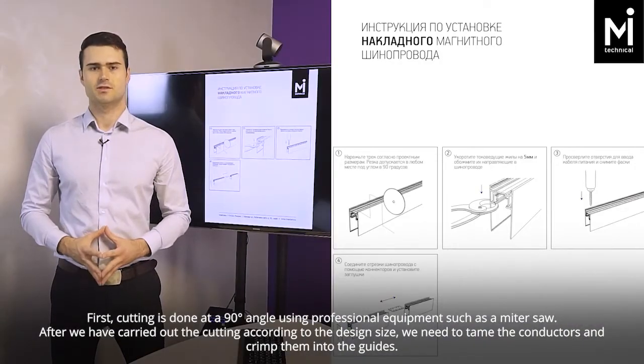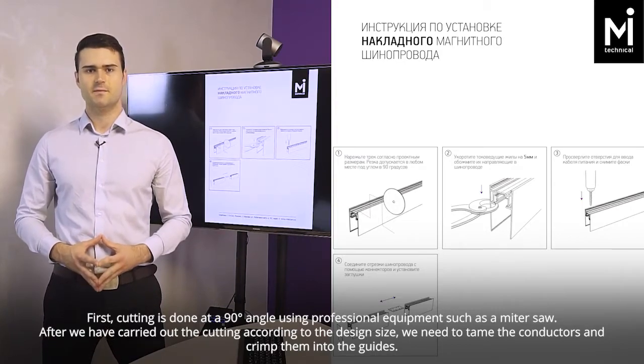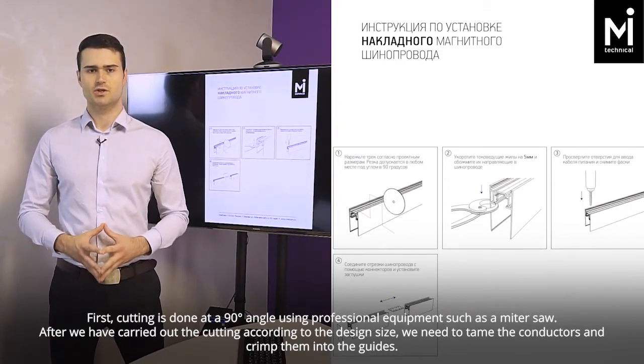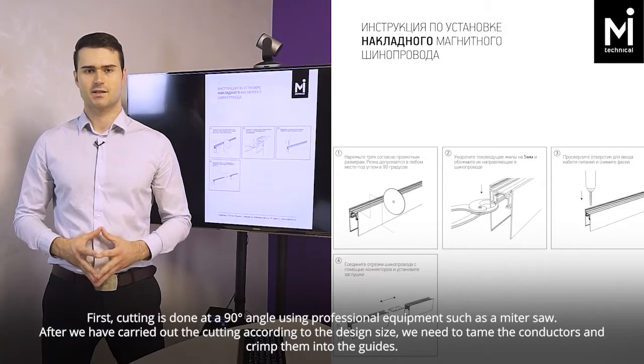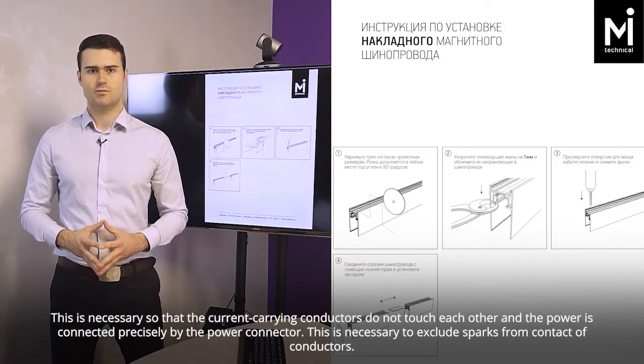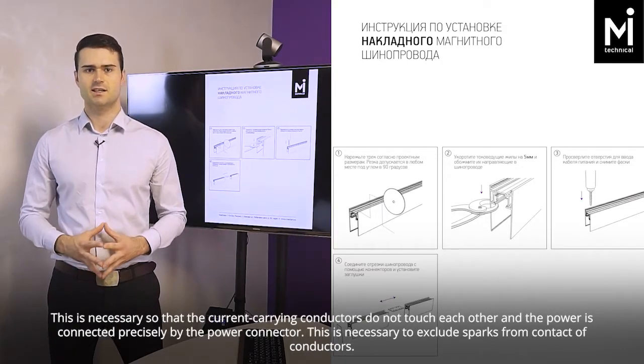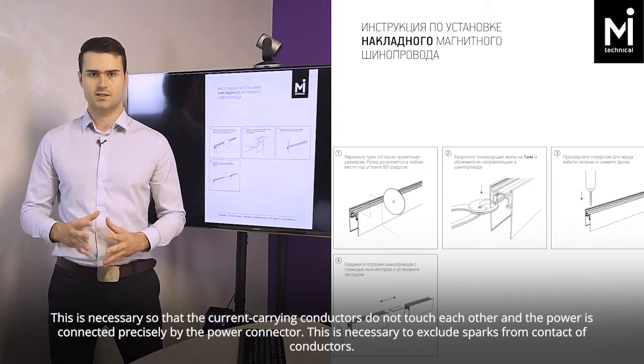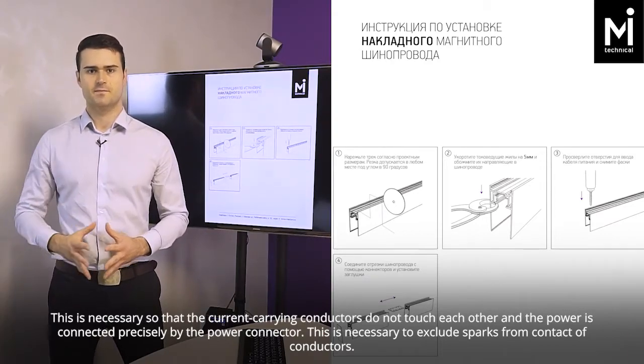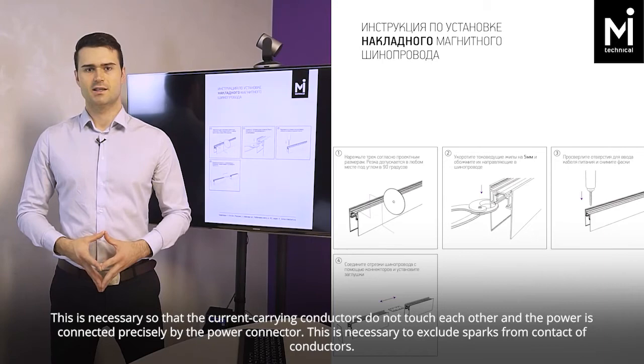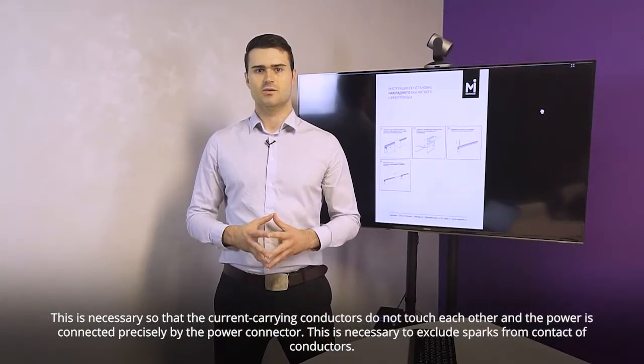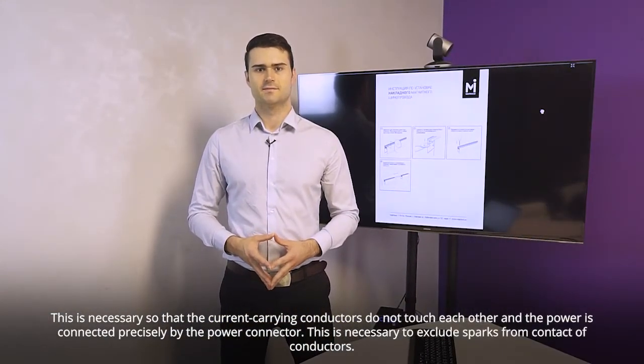After we have carried out the cutting according to the design size, we need to tame the conductors and crimp them into the guides. This is necessary so that the current-carrying conductors do not touch each other and the power is connected precisely by the power connector, and to exclude sparks from contact of conductors.